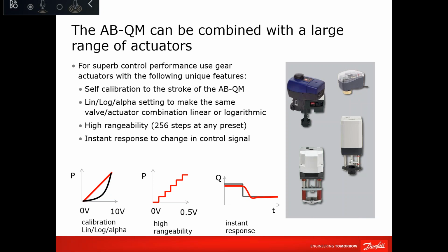High rangeability. If we take the smallest actuator we have, 256 steps. The minimum of the smallest actuator is 256 steps, which means if your valve total stroke is 2.5, it will be divided by 256. Then you can move your valve spindle by 0.01 millimeter if required by the control sequence, because in case of a normal control sequence, you have a half volt movement, half VDC. In some of the BMS application, this can go up to 0.01 or 0.02 VDC. In both cases, the actuator can respond to that.